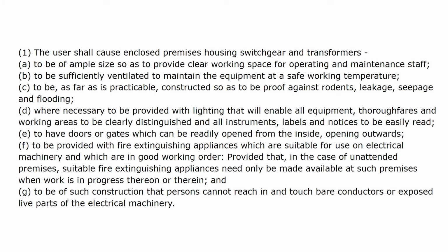The user shall cause enclosed premises housing switchgear and transformers A. To be of ample size so as to provide clear working space for operating and maintenance staff. B. To be sufficiently ventilated to maintain the equipment at a safe working temperature. C. To be, as far as is practicable, constructed so as to be proof against rodents, leakage, seepage, and flooding.